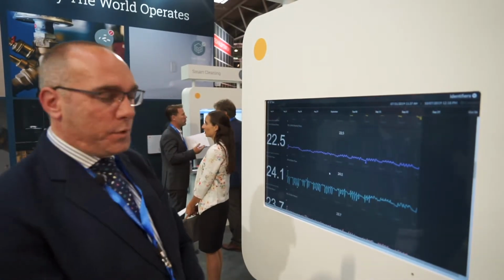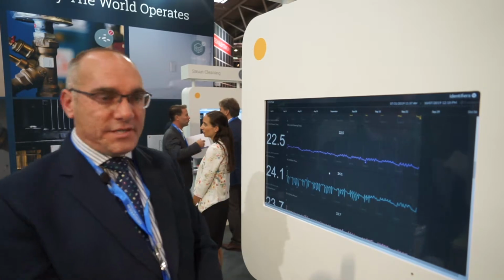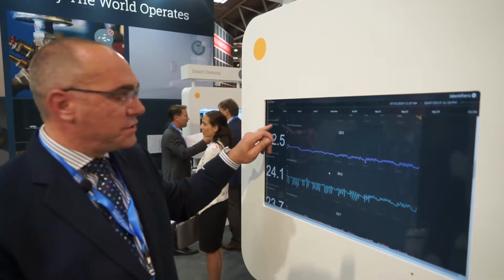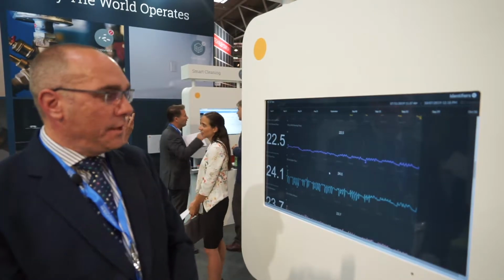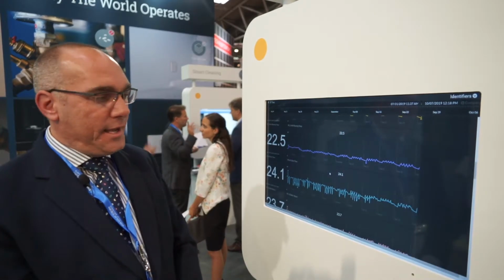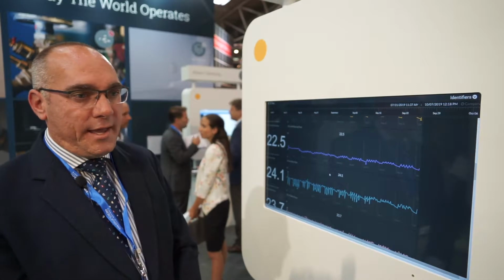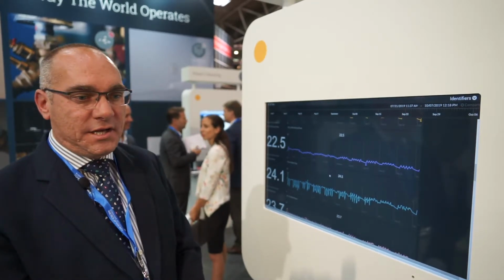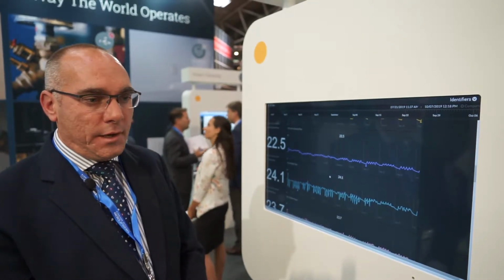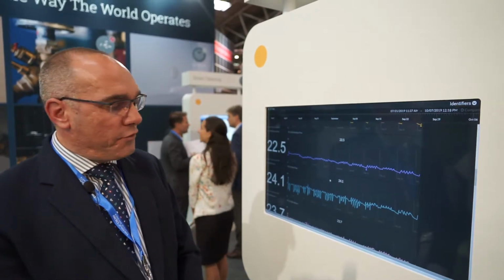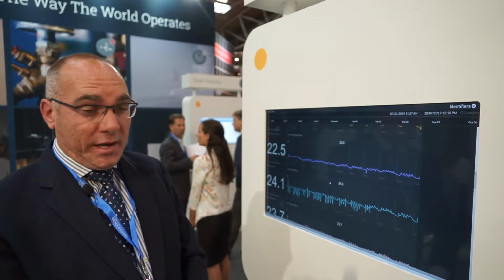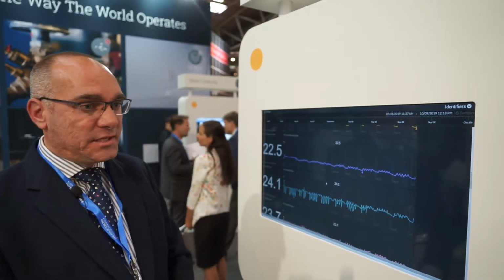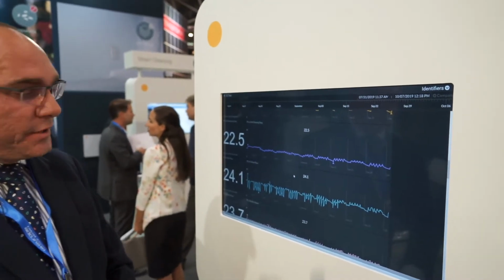Another very good example is where we take the temperature sensors and apply them onto motors and bearings to monitor heat transfer, which means that we can see if a pump or a motor is running inconsistently and starting to develop more friction through bearing wear. Based on that data, we can quickly assign an action and corrective action with our remote monitoring facilities.